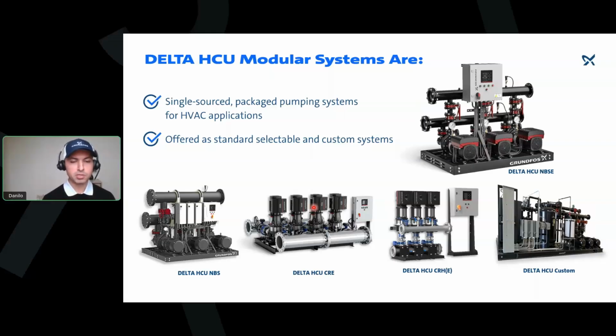When we're talking about part load conditions, you want to have at least, let's say, one pump sized for 50% load, and then you may be able to achieve 100% load with all the pumps, and then you can add redundancy if you want to or not. And nowadays, with technology and improvements in manufacturing, as you can see in the pictures and example, you can increase the number of pumps and actually save on footprint because of packaged solutions, right? So it's very simple nowadays to save on space, increase modularity, and increase energy efficiency.